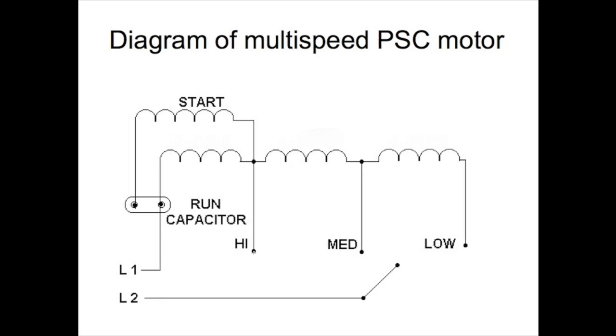This switch, if it goes to high, then it simply goes right through that short portion of the run winding. That's going to be the highest speed because it has the lowest resistance.